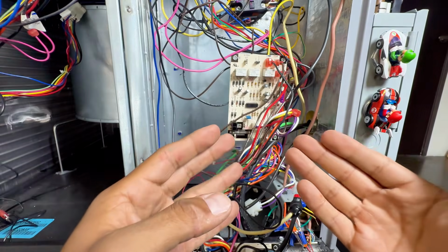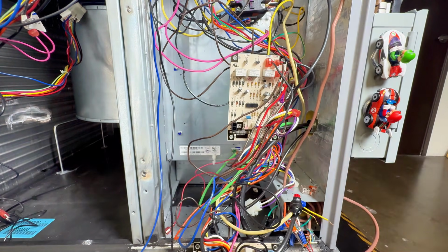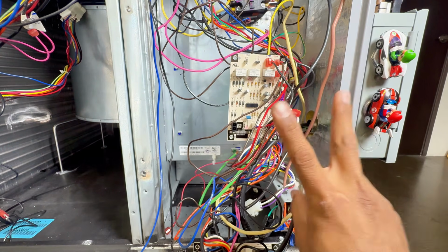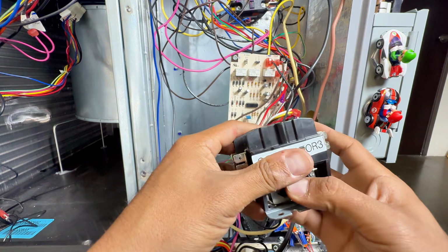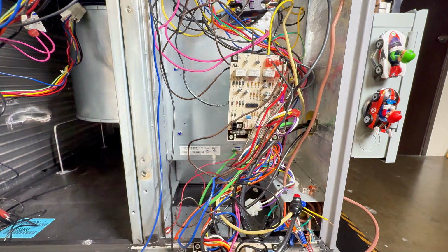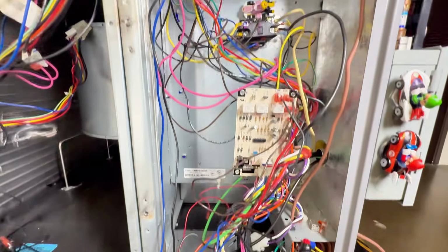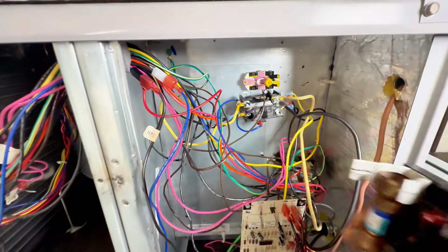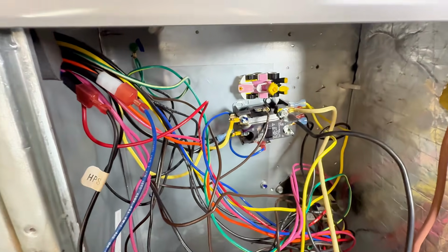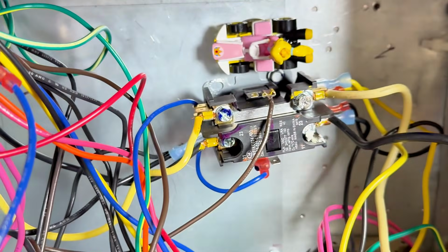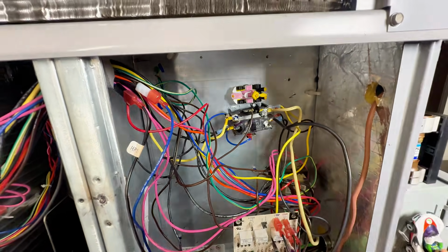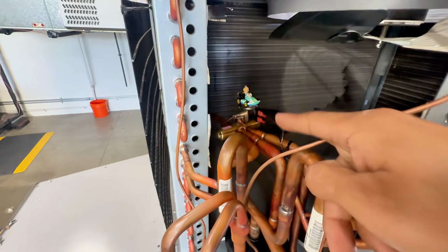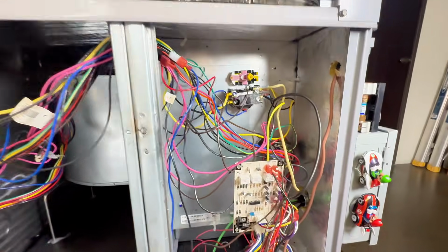The nice thing is that common's already at the coil. So remember, we're dealing with two coils, two loads, your contactor coil and your reversing valve. So we have here Peach, she's already at this contactor coil on that side. I pulled the disconnect, so there's no power. But brown wire, common, she's already there. She's waiting for Mario to work things out, okay? They got to work things out. And then over here, you got Rosalinda, that brown wire is common. She's waiting for Luigi to work things out, okay? So here we go. Where do we start?